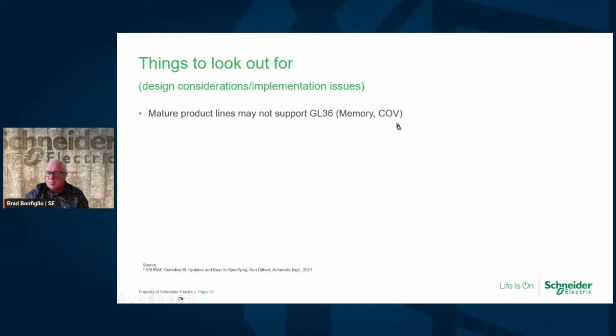Application-specific controllers by the BTL profile don't support or don't have to support COV. And if you think about that, that's change of value. If you don't have that available, you're going to have to ping the network even more than you had normally with just using Guideline 36. And it's going to pretty much bog down the network. So then you have a real challenge of, will it even work? That goes back to that theory of, can it even work or not?